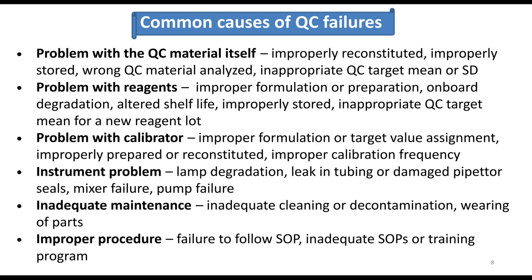QC can fail due to inadequate maintenance, so inadequate cleaning or decontamination, wearing of parts for the instrument, and also improper procedures. So QC can fail because the techs fail to follow the standard operating procedures of the lab, or the SOPs are inadequate, or the training program is inadequate. So there are a lot of causes for QC failure, so it can be really difficult to know where to start once a QC alert is received.